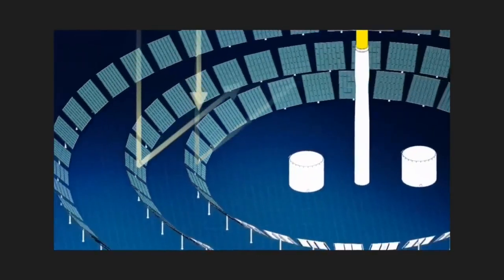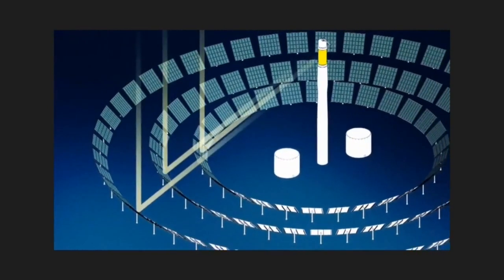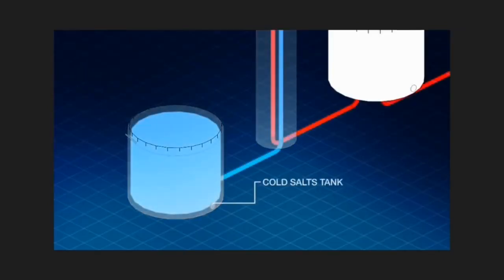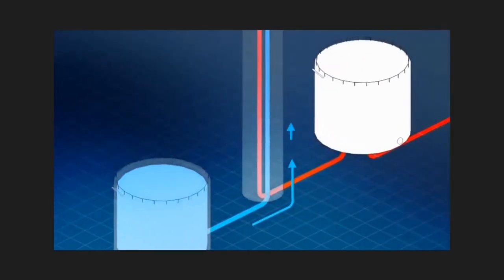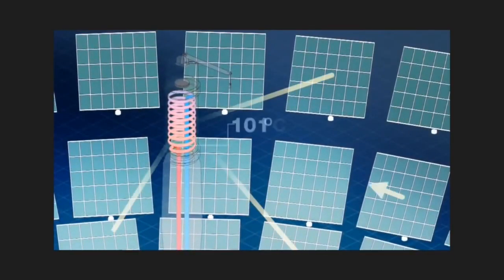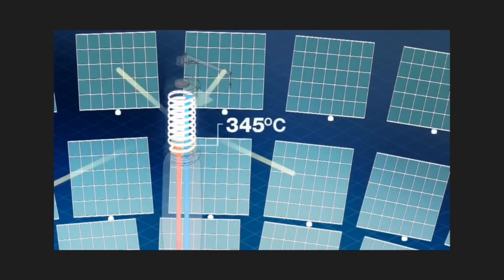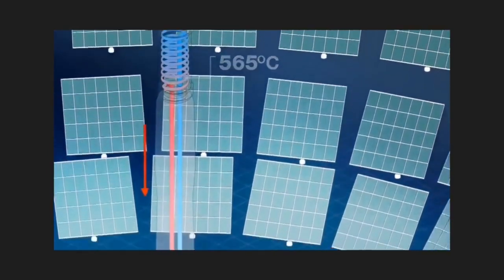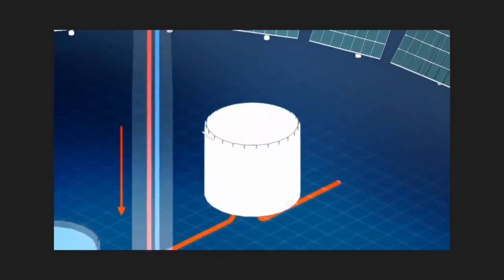Sunlight is reflected from each heliostat onto a central receiver at the top of the tower. Sodium and potassium nitrate salts are pumped from the cold salts tank up to the receiver where they absorb the concentrated solar thermal energy, reaching temperatures of up to 565 degrees. The heated salts are then pumped down to the hot salts tank where they can be stored in a molten state or used to generate electricity via the heat engine.